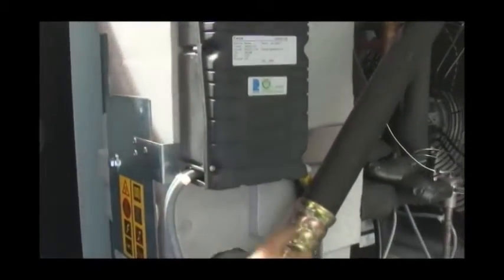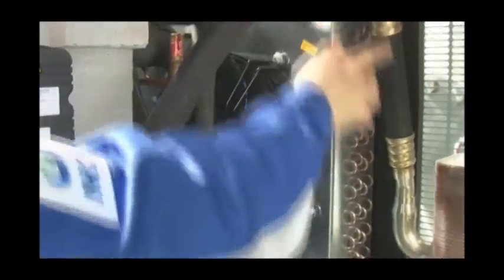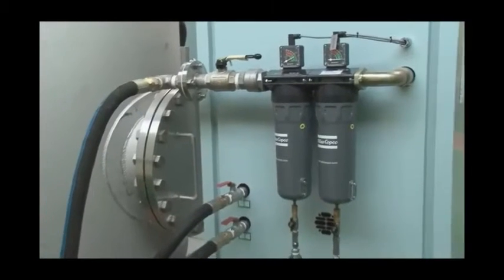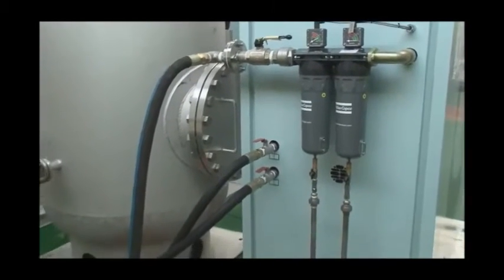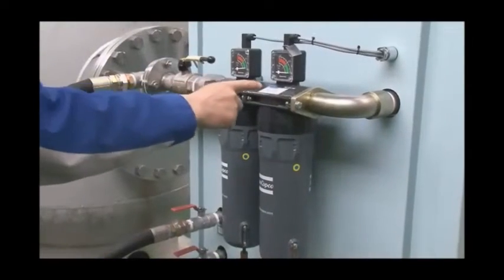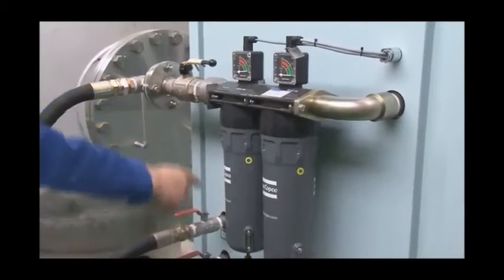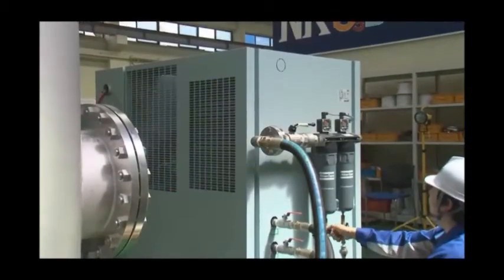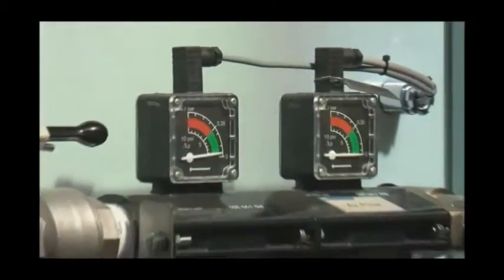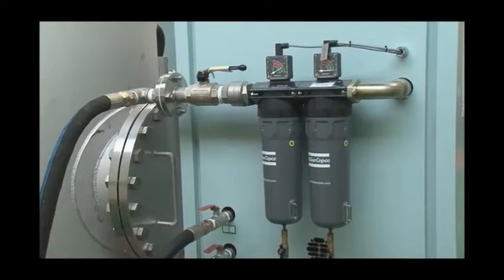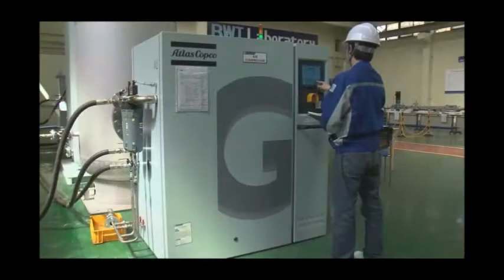The refrigerated type air dryer is integrated in this compressor to dehumidify the compressed air and keep air temperature between 4 degrees and 38 degrees Celsius. And air coalescing filter assembly is fitted as a package and remove particles bigger than 0.01 micron, and keep air from oil contaminations less than 0.01 ppm. To keep air quality using air dryer and filter assembly is very essential for next process of oxygen generator, and the condition of dryer and filters shall be checked and maintained in good order.